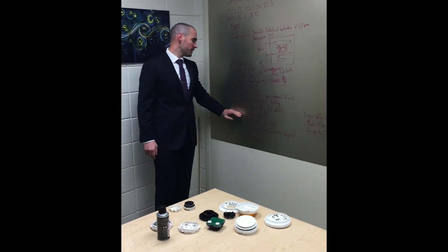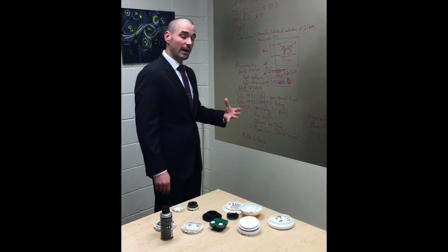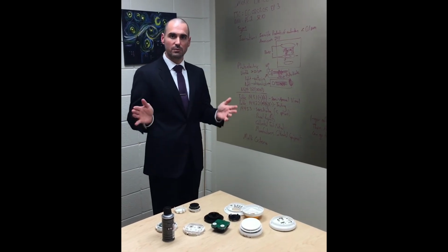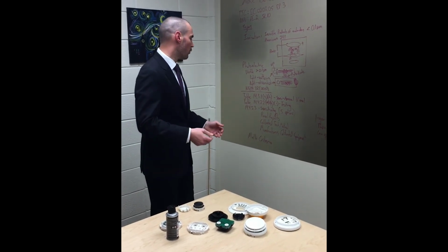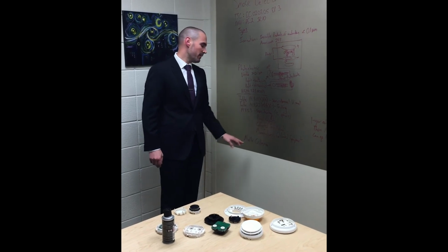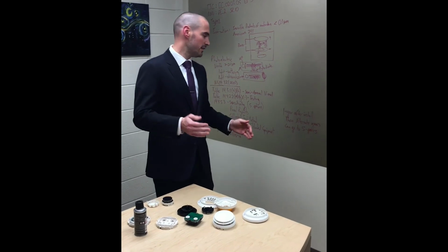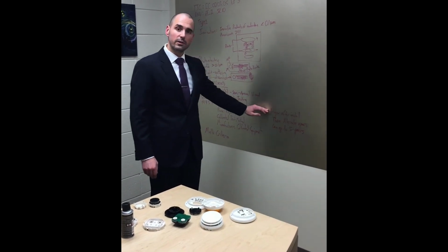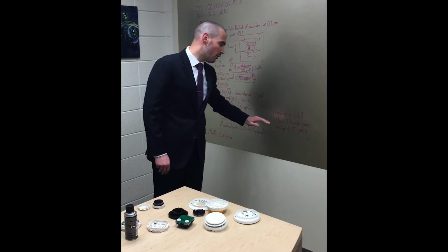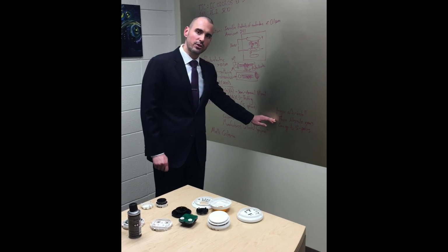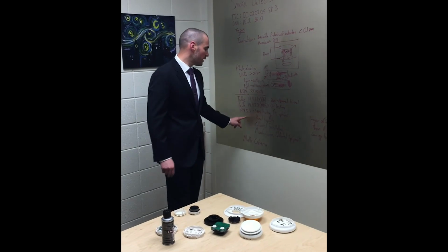Then section 14.4.5.3 talks about sensitivity. There are 5 different options there. Most common for addressable systems is panel reports. It's an addressable system, so it can pull the sensitivity and you print out a report. You can also do the calibrated test method with manufacturer calibrated equipment. We talked a little bit about these in previous videos, but just real quick: 1 year after install, you have to do a sensitivity test. Then after it's calibrated, you can do alternate years. And after the second calibration, as long as everything is fine and you're not having issues, you can go up to 5 years. So go back and check that out.